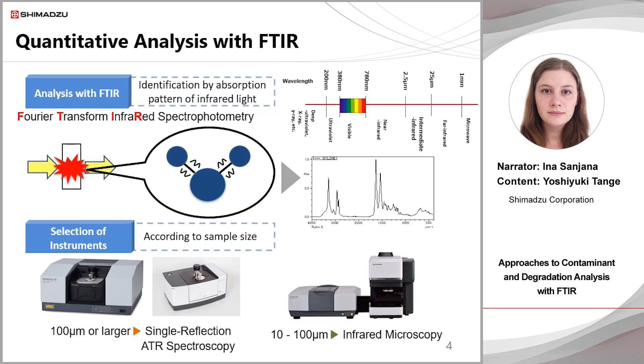Next, we need to select an instrument according to the size of the sample. If the sample size is 100 micrometres or larger, then single-reflection ATR spectroscopy is suitable. Infrared microscopy is used when the sample size is between 10 and 100 micrometres.